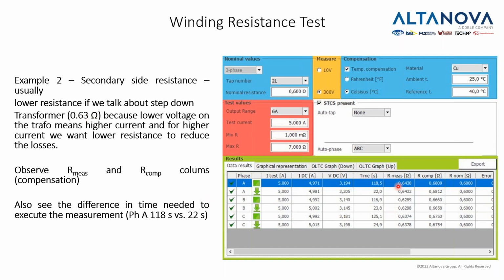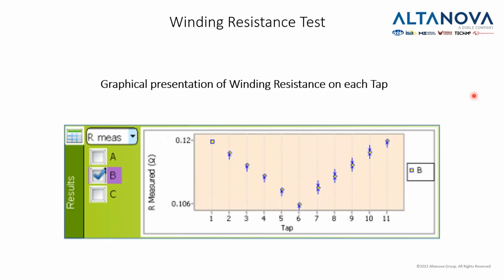We can also see the columns measured value and compensated value because, for example, right now it's 25 degrees, and I'm comparing this to the result, which was obtained at 40 degrees. Now, another thing to take into account is a graphical representation of the results, and this is how this would look like when you do 11 positions on a tap changer.